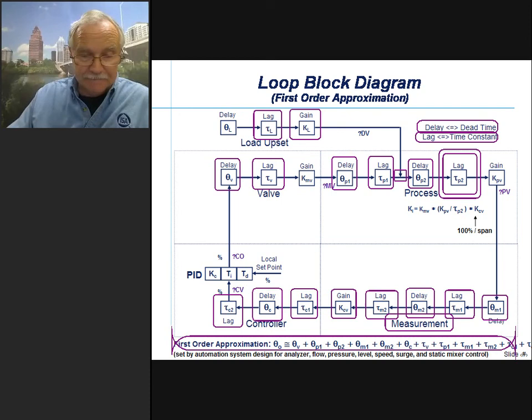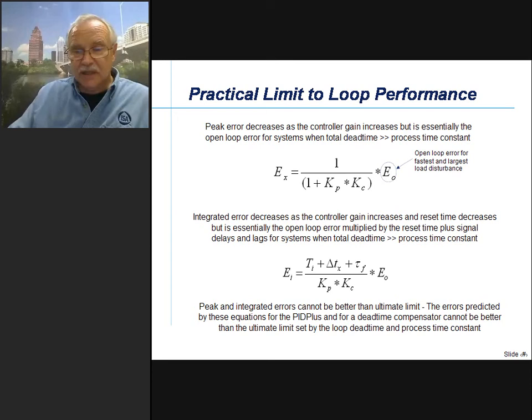And if you think about it, you as an automation engineer, by the settings you choose for analyzer, flow, pressure, level, speed, surge, and static mixer control, are really setting the biggest part of the total loop dead time, because for these applications the process dead time is rather small. We've seen this before.